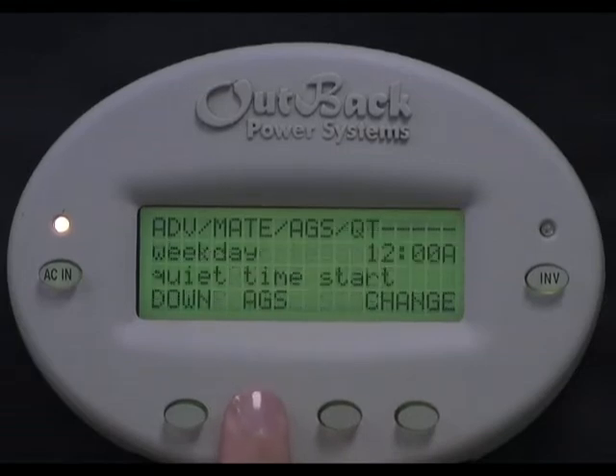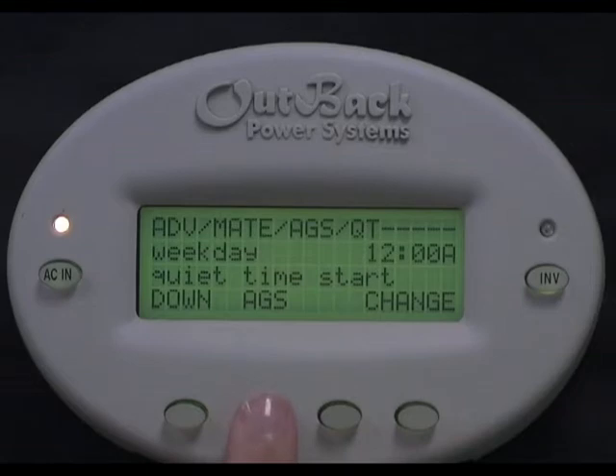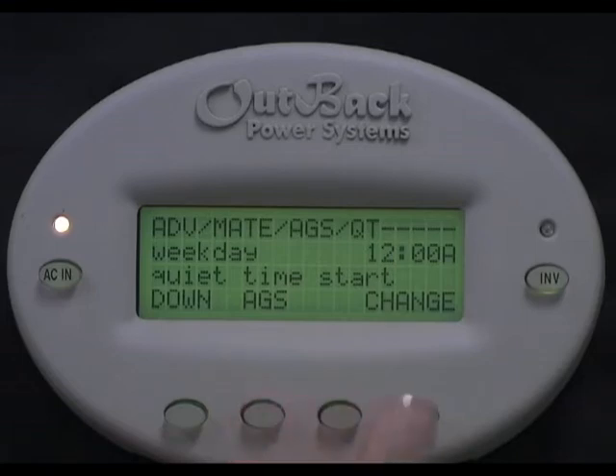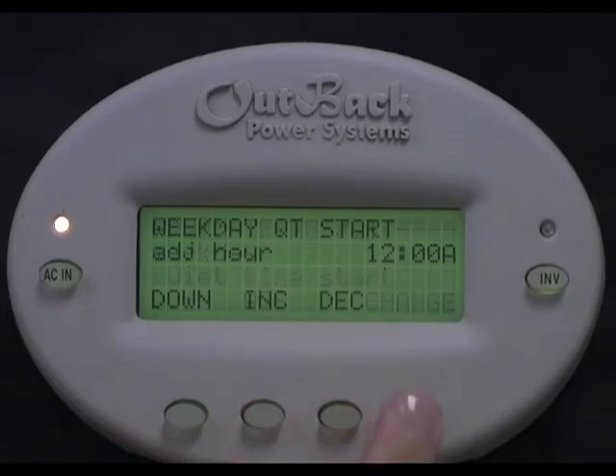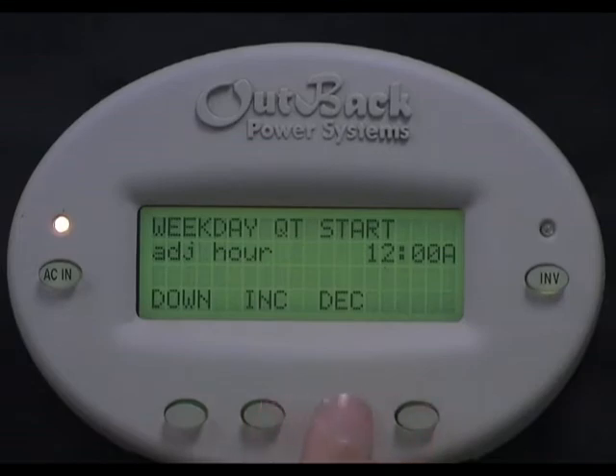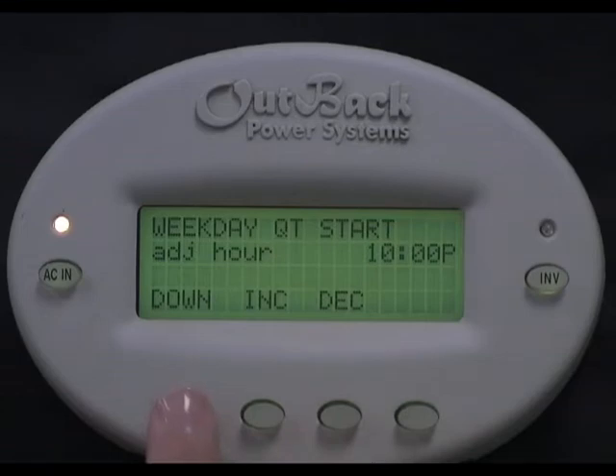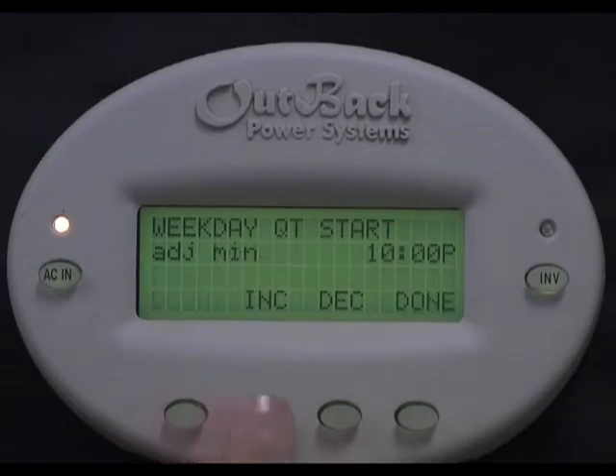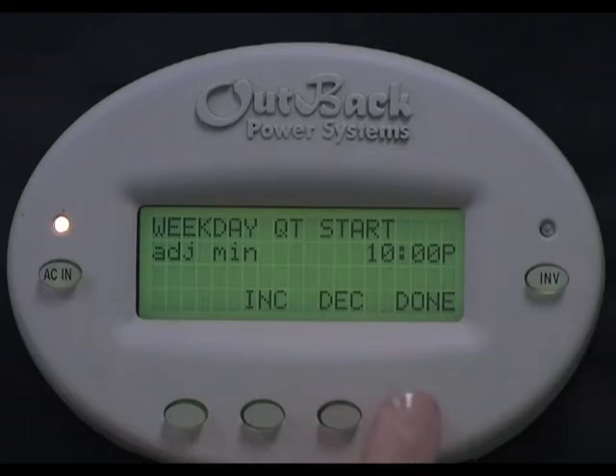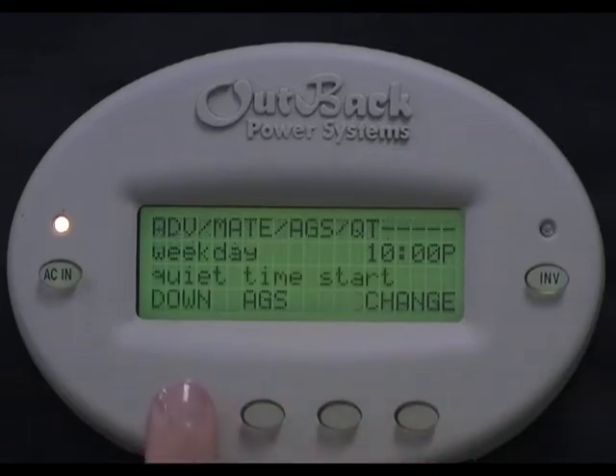Weekday Quiet Time Start is the start of the time period when you don't want the generator to run Monday through Friday. For instance, if you don't want the generator to run between 10pm and 6am, you would set this time for 10pm. To set it, select Change, then Increase or Decrease to adjust the hour. Select Down, then Increase or Decrease to adjust the minutes. Select Done, then select Down.